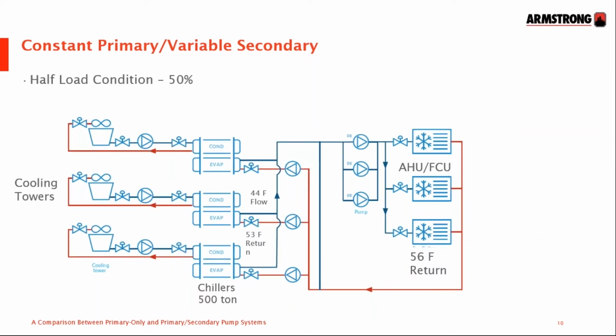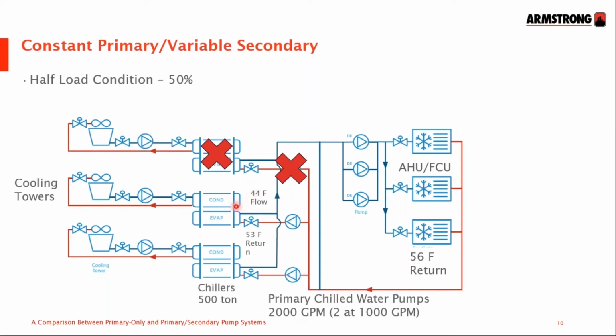Let's look at half load. Using load-based sequencing, we turn off 1 chiller. And now we have 2 1000 GPM dedicated pumps through 2 500 ton chillers, both 3/4 loaded, cooling that water from 53 to 44 for a 9-degree delta T.